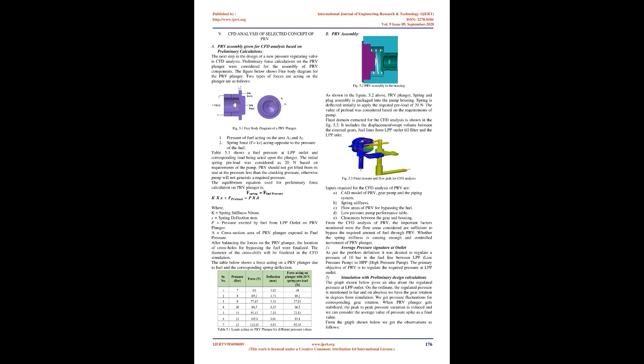Spring-controlled flap type PRV. Spring-controlled flap type PRV is shown in Figure 2.9. It consists of a flap with a spring attached to it which exerts pressure on it. The working principle of this type of PRV includes both spring force and gravitational force. When pressure increases beyond the preset pressure of the spring, the flap opens and the fuel goes to the outlet of the valve, which further goes to the return line. When pressure is reduced, the spring forces the flap back to its original position, closing it. Due to this, flow to the outlet of the valve is stopped. Schematic of spring-controlled flap PRV.